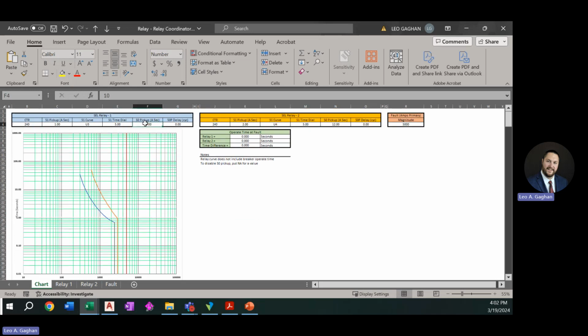But if I wanted to move this out to, let's say, 20 seconds, or sorry, 30, we can now see that fault lies on the inverse time portion of our curve, and now the operate time is about half a second. And there's about a half-second difference in operate time between the two of these because our other one still operates instantaneously.